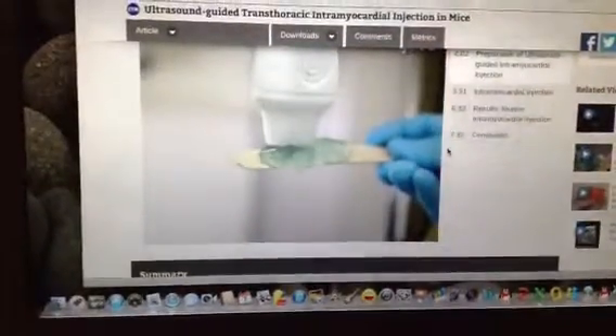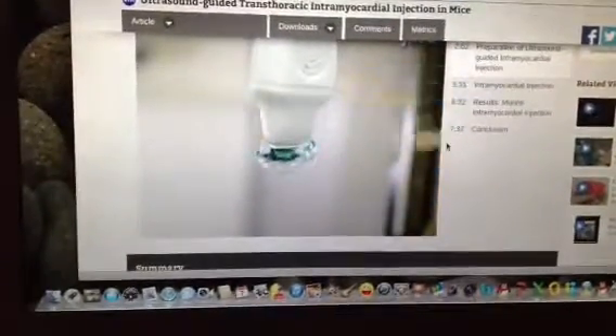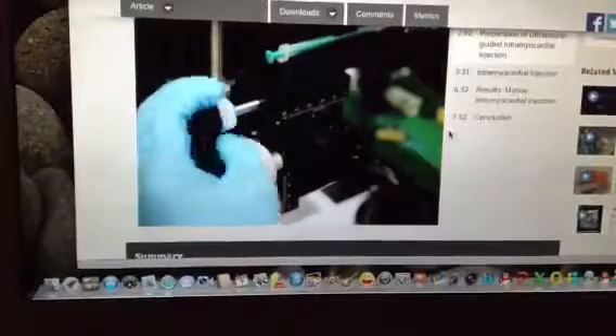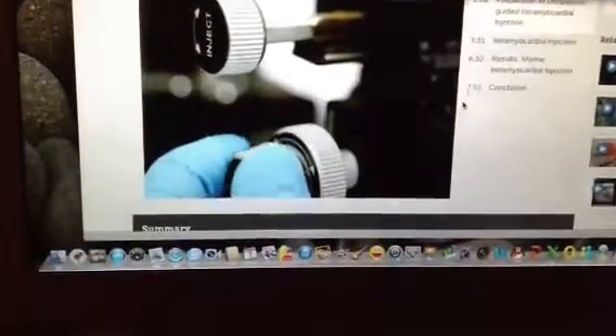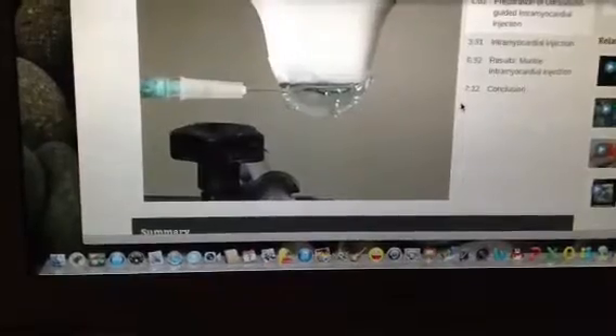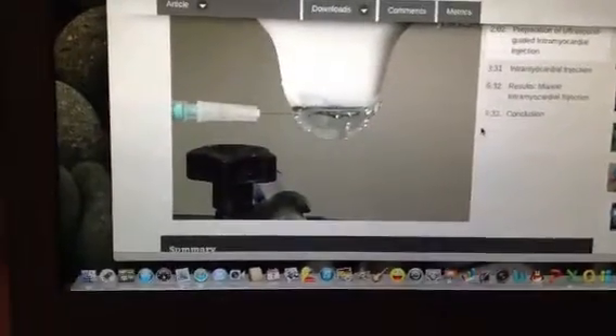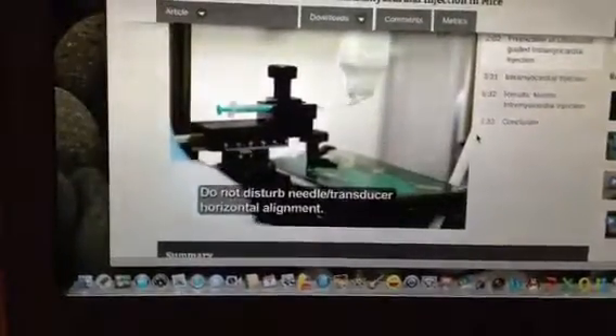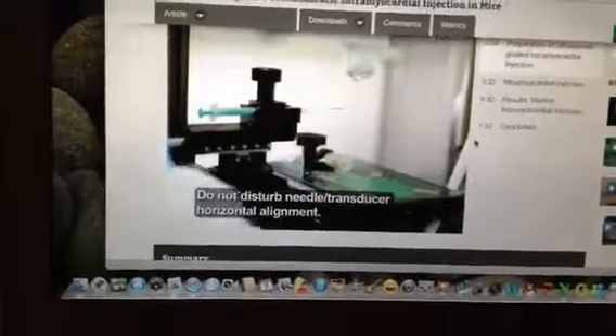Next, liberally apply ultrasound gel to the transducer head. Carefully unsheath the needle and use the needle mount controls to advance the needle directly under the transducer and within the ultrasound gel for visualization. Use the needle mount control to make minor adjustments so that the needle can be clearly seen along its length on the ultrasound image. Then use the scan height control to move the transducer superiorly from the animal platform to allow placement of the anesthetized mouse onto the animal platform.